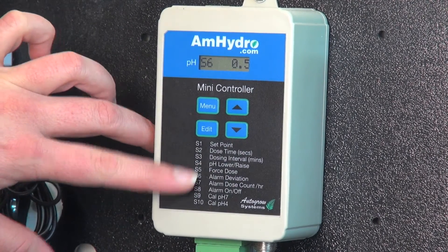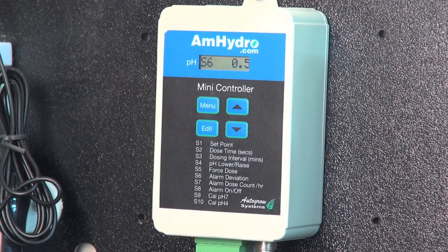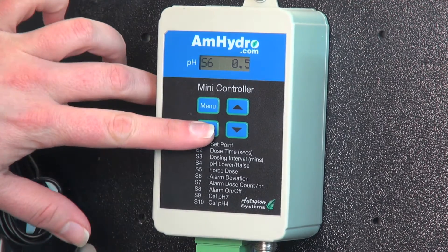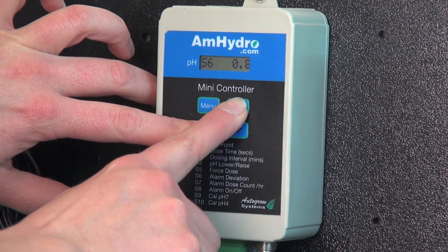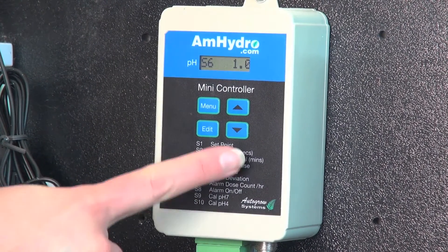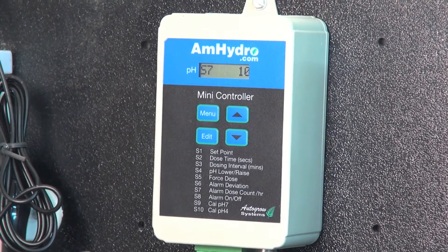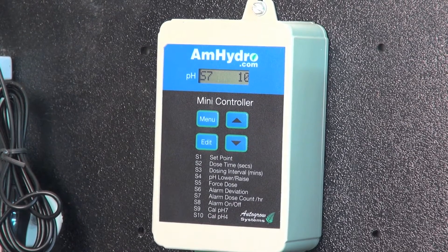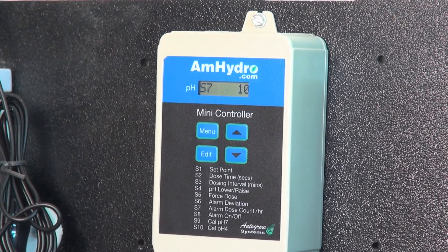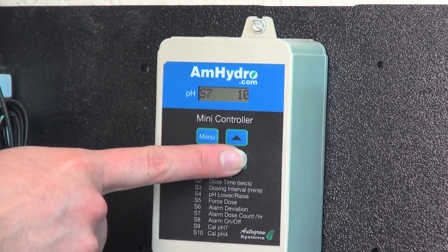We have the alarm deviation, S6. Right now it's saying that if it goes 0.5 outside of your set point, the alarm will go off. This is probably a little bit tight, so I'm going to change this to 1.0 — so if it goes below 4.9 or above 6.9, it'll set off an alarm. You also have your alarm dose count per hour — currently set so that if it doses more than 10 times in one hour it sets off an alarm. That would give you a heads up that maybe something is wrong with either your solution or the probe.